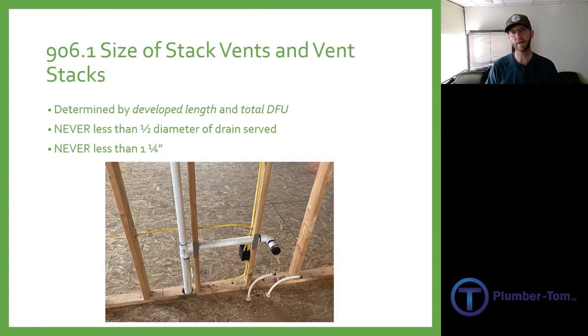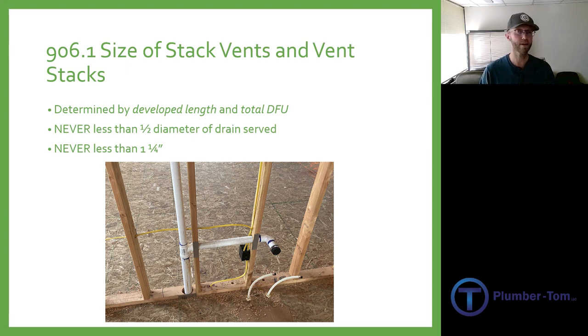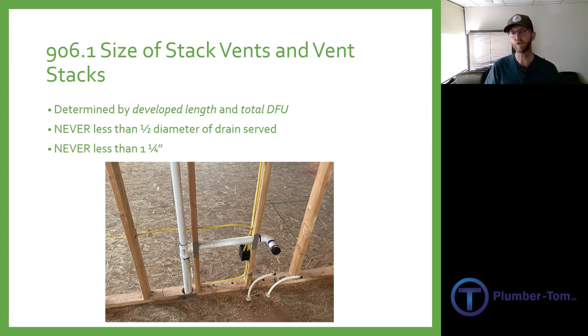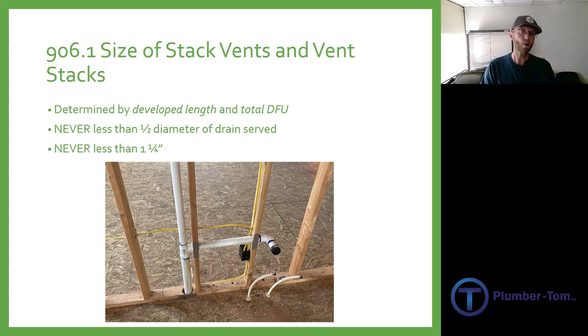Some minimum requirements for the sizing of vents: first, it's never going to be less than half of the diameter of the drain served. So if it's a four inch pipe, the vent should never be smaller than two inches. Three inch pipe should never be smaller than one and a half inch for the vents. But there is also a limit of one and a quarter inch — the vent pipe itself should never be smaller than one and a quarter inch. So if you have a two inch pipe, you might think you could run a one inch vent, but that's not acceptable. One and a quarter is the smallest you would ever run for a vent pipe.